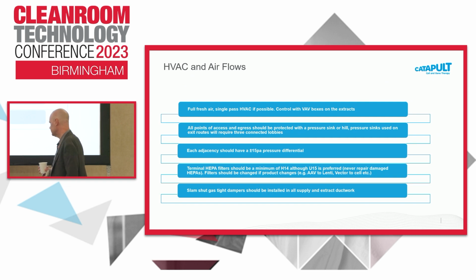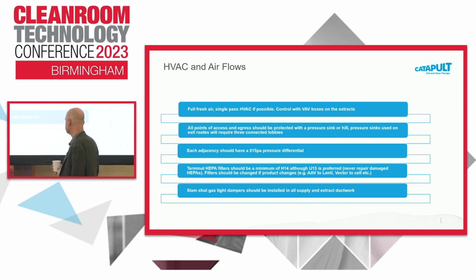I'm sure I'm preaching to the converted. Long gone are the days when this was repaired. I don't ever think to repair a damaged HEPA - if it's damaged, replace it. And also, at the end of a campaign of a particular biological entity, what we would tend to do as part of our campaign clean down and change is use vaporized hydrogen peroxide to fog the entire room, and then we would change out the HEPAs and go again.